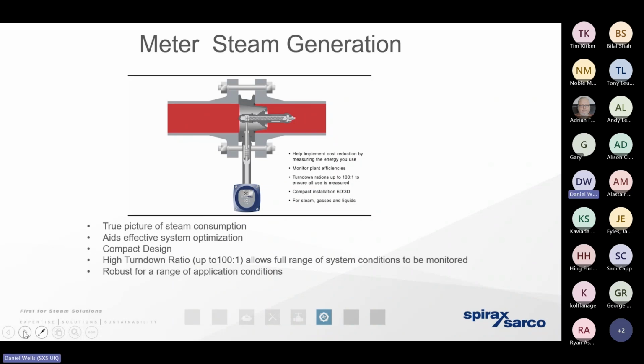But it's only by measuring the steam, metering the steam, that we can have confidence in where those inefficiencies may lie. And if we were to repair or rectify those inefficiencies, we're going to want to have an understanding of what the payback is, what the benefit is, how much steam we've saved, how much gas we've saved, and the extent to which we've now reduced those carbon emissions.